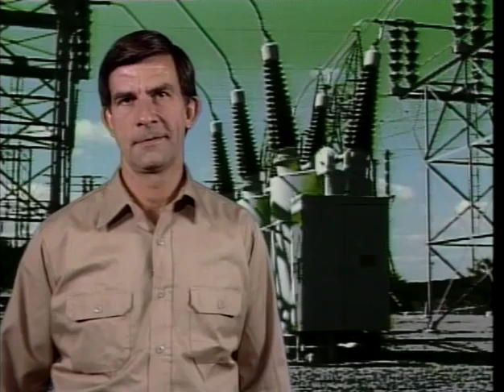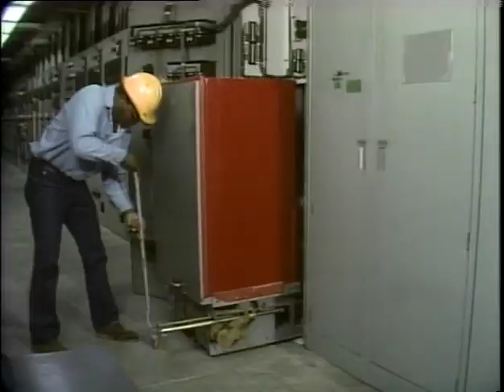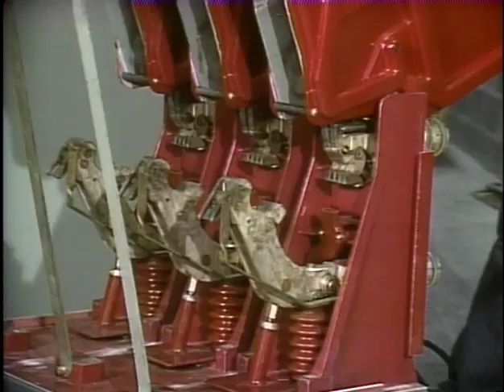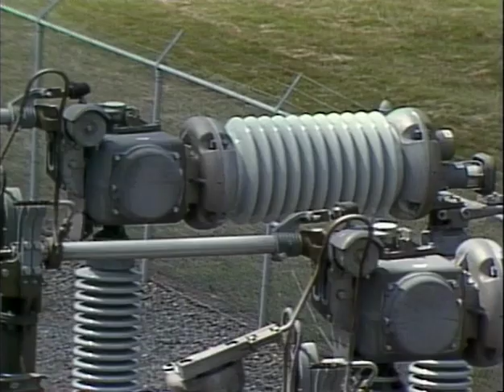We'll see how switching is used to de-energize a circuit and how tagging can help prevent a circuit from becoming energized accidentally. Now, switching is performed by using protective devices to energize, de-energize, or isolate circuits. You should already be familiar with two of the most common switching devices, circuit breakers and disconnect switches. Circuit breakers can be used to energize or de-energize electrical circuits. To energize a circuit, switch contacts inside the breaker are closed. This allows voltage to pass through the breaker and energize the outgoing circuit. To de-energize a circuit, the switch contacts are opened, breaking the circuit and removing power from the line.